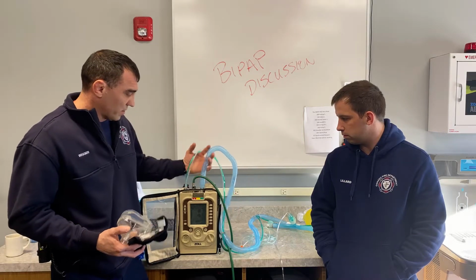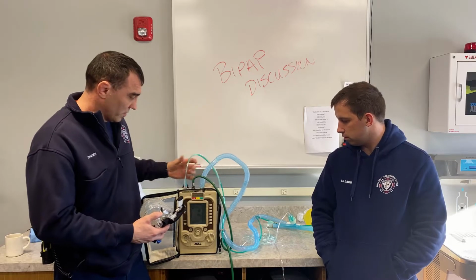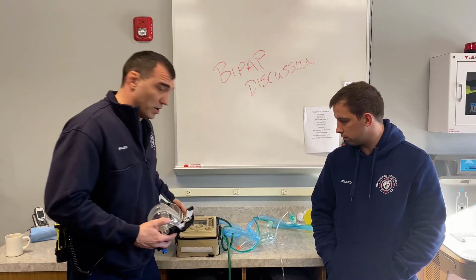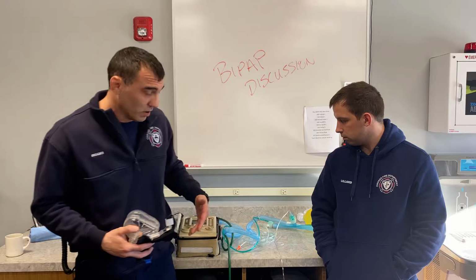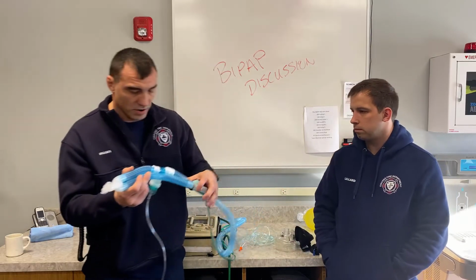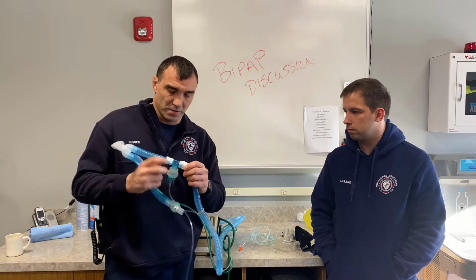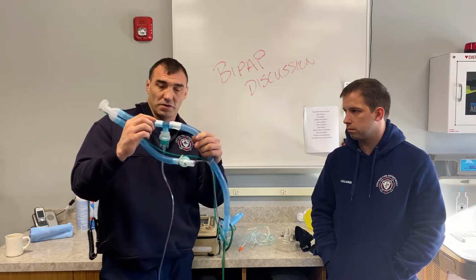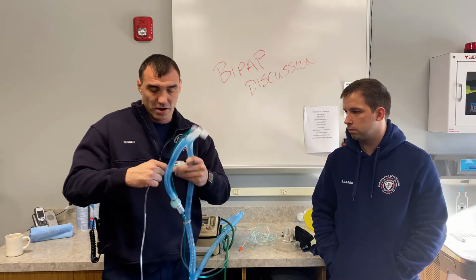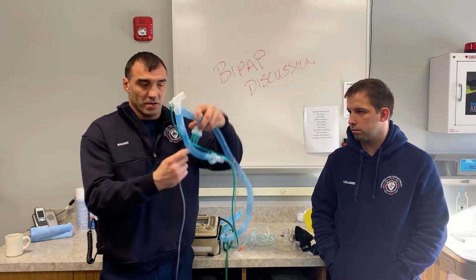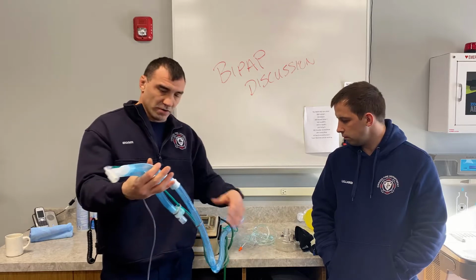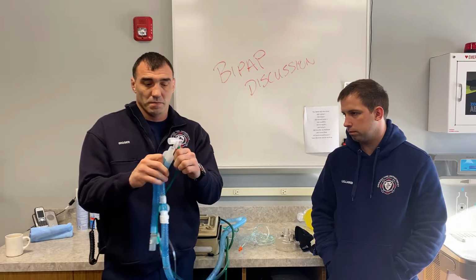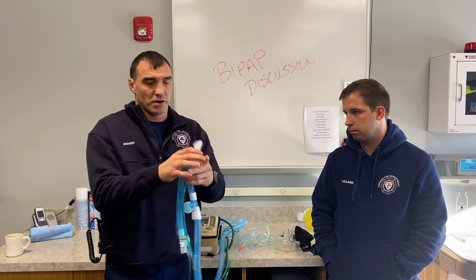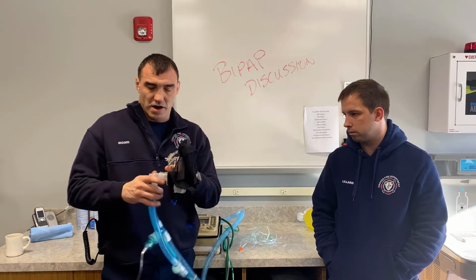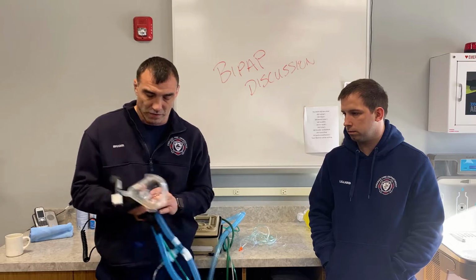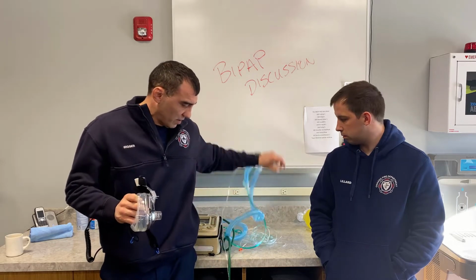I have that disconnect, I start, just like Pac said, at the vent and start looking. Is this on, obviously? Is my transducer on? And my exhalation port, are they on the correct fittings? If they are, then you work your way up the vent and we make sure. This training tube has a breathing treatment in it, so you'll notice that I taped it before and I put this in there. This could be the place that there's a leak, or possibly this hose came off and there's a leak. So anywhere along this, just look along your setup. These right here will come off, be popped out just like that. Running that way, you'll have a leak. So just work your way down all the way to the mask and make sure that you have a good seal on your mask. The next is the mask itself. Pretty much every vent works the exact same way.